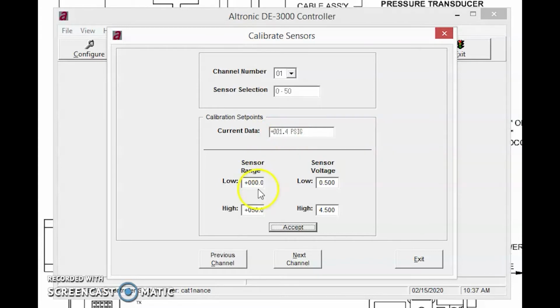Now down here in the bottom, it also tells me that the sensor range is 0 psi equals 0.5 voltage. Tells me for the high range, 50 psi equals 4.5 volts. So what I've done is I have measured the voltage that's coming into the channel, and when I recorded it, it was feeding me back a voltage of 0.619. Now I actually did that right at the channel.